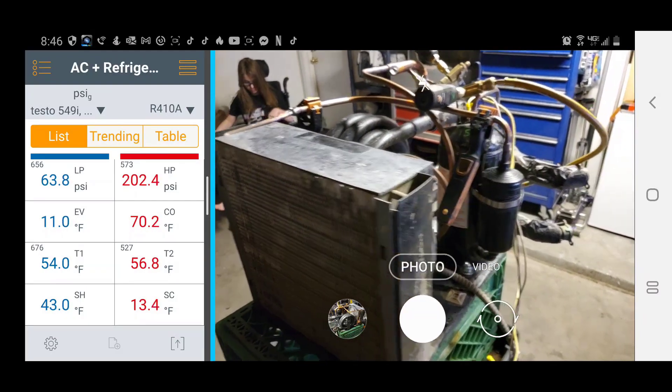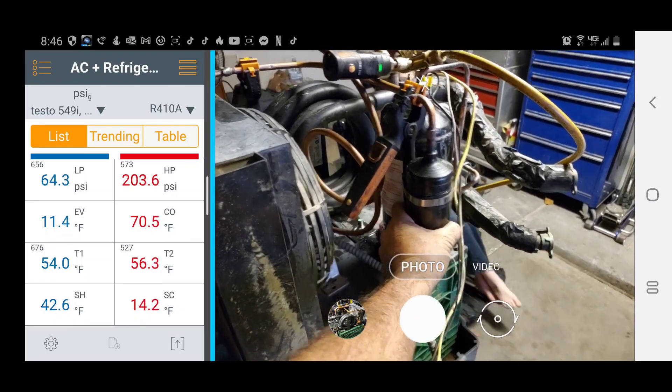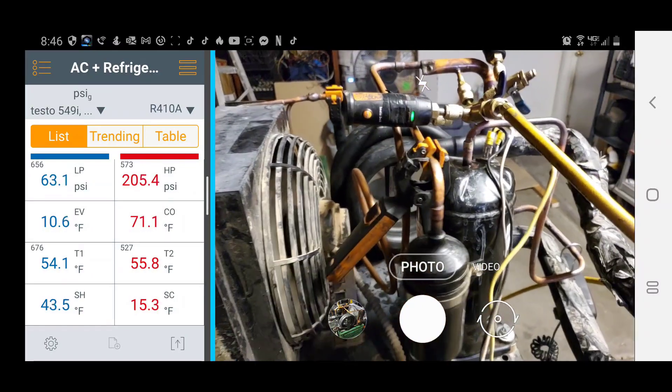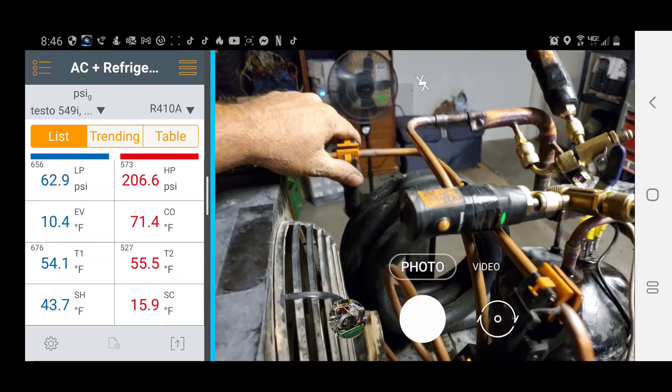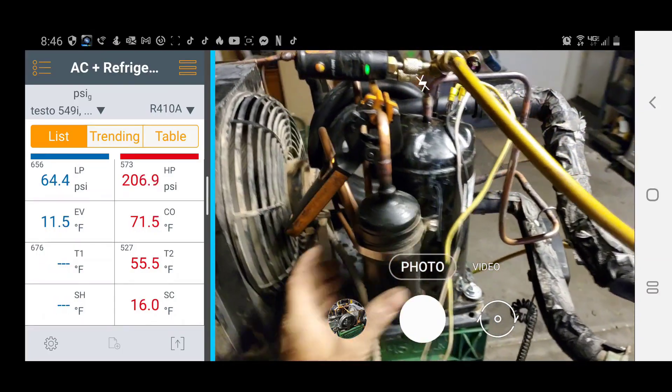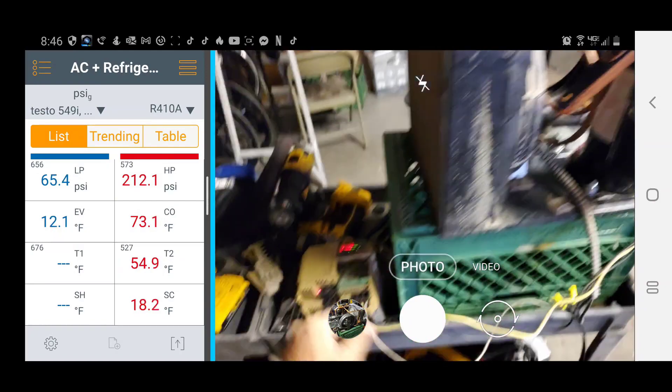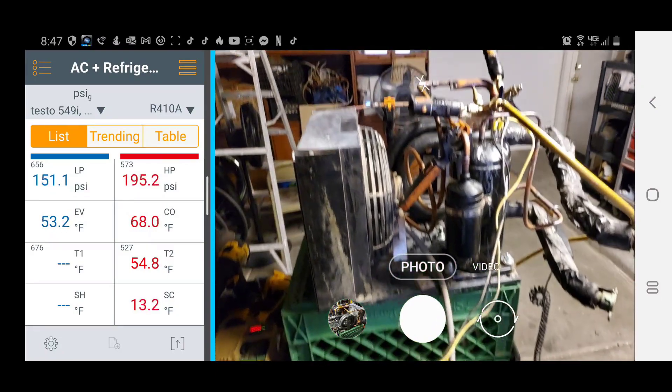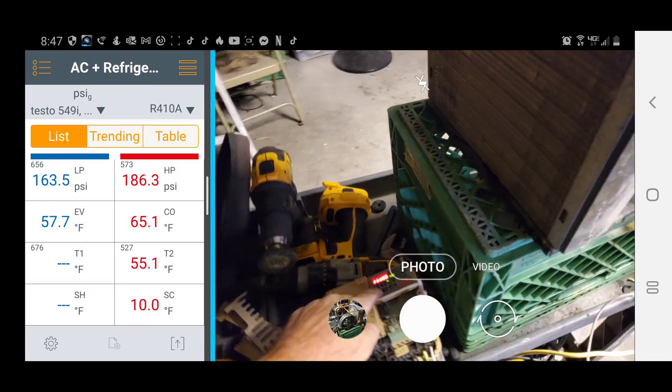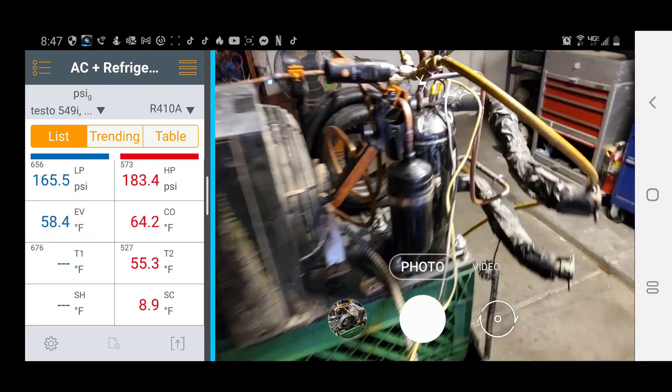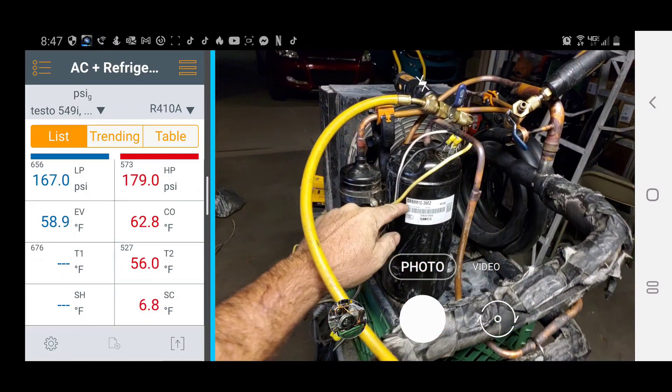But this thing—it's like the compressor gets tight or something and it pulls overload on the VFD. Listen to that vibration. And this suction feels way cool compared to the line up here, so something's going on. Maybe there's a restriction? No, it can't be because I'm reading my pressure right here. It's just weird because the suction line isn't all that cold to grab. It's 54 degrees, which is the temperature out here, but yet it's really cold on this accumulator. When I turn up much more it starts wigging out. It overloaded, and when I put my amp meter on there it shoots up to over 15 amps per leg, which is already pulling more than it should.